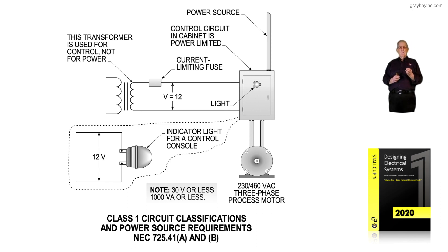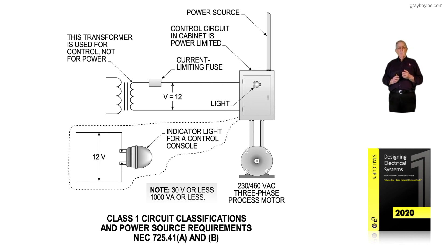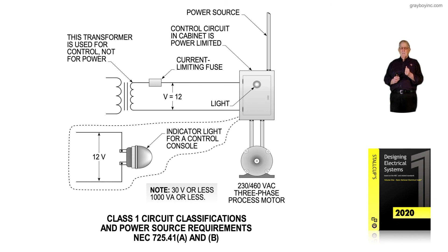This low voltage may only provide power to an indicating light — green when the circuit is energized, red when it's not. The key question is: how are we using it? Are we using it as control, or to power indicating lights? This circuit can be a Class 1 power-limited circuit as figure 4-14 indicates.